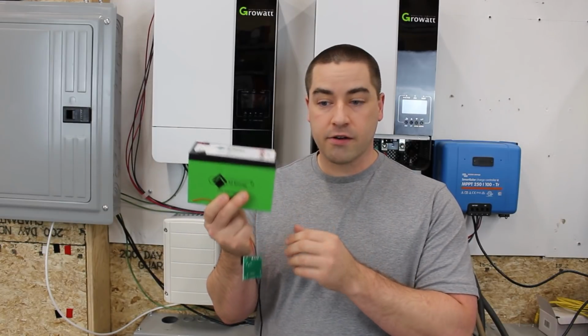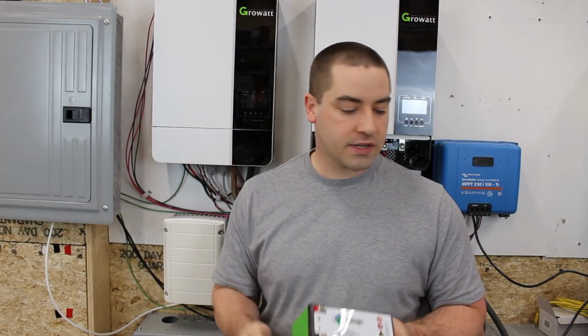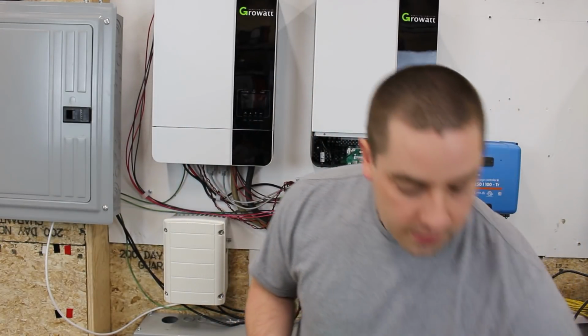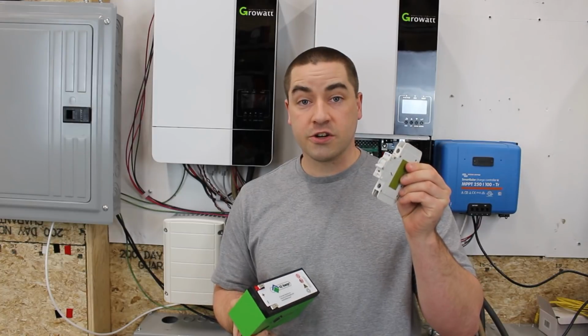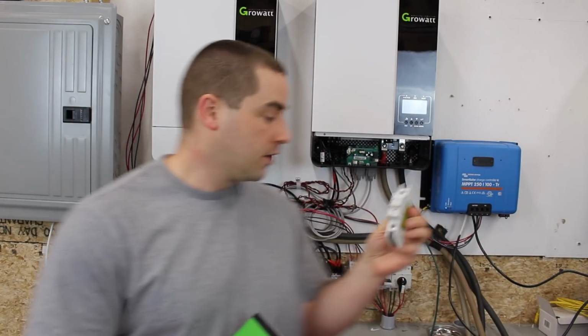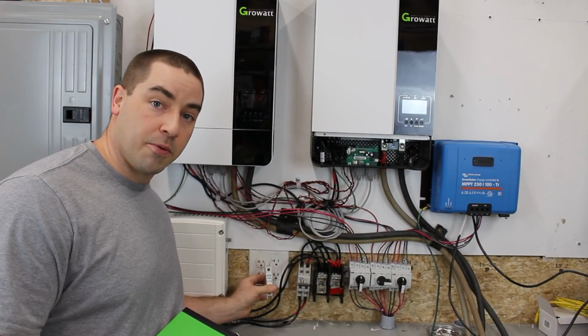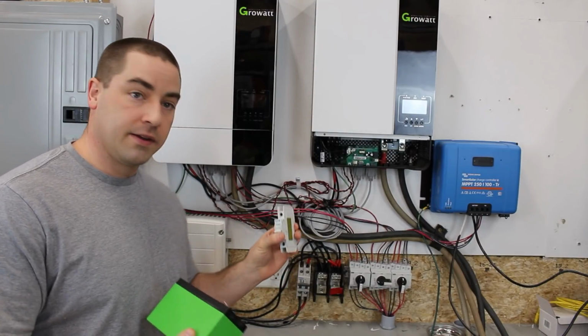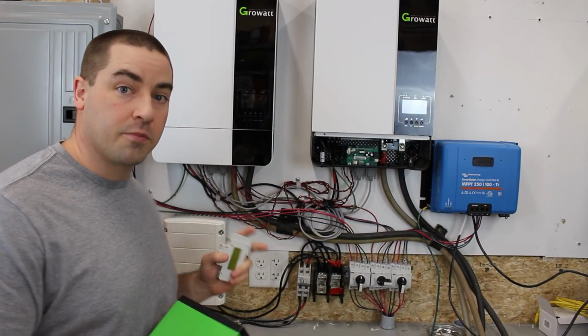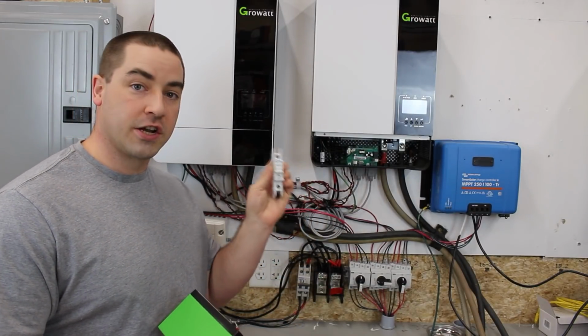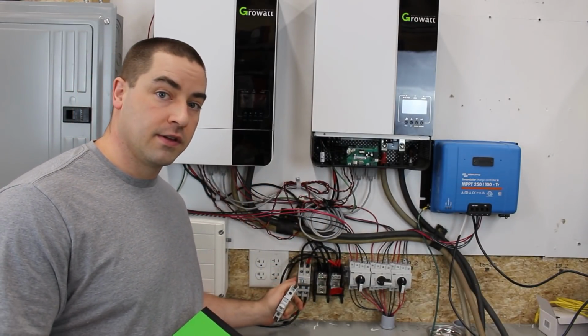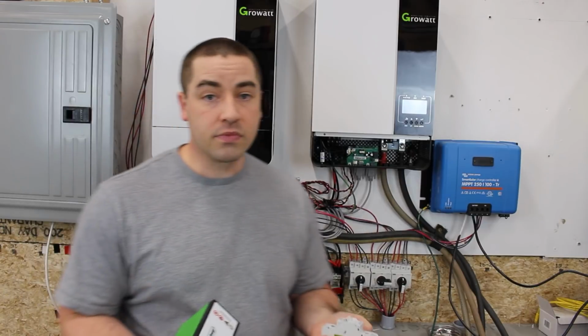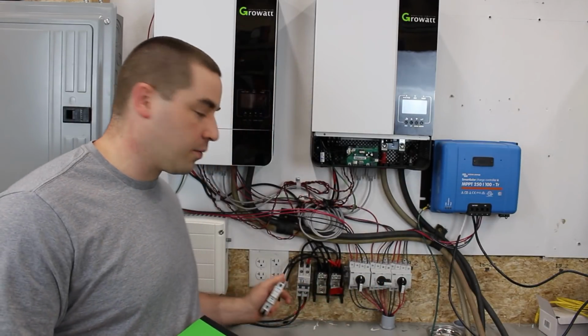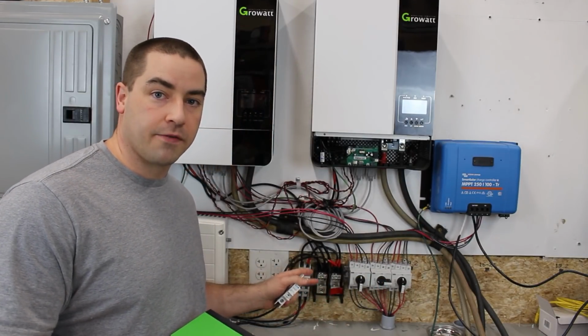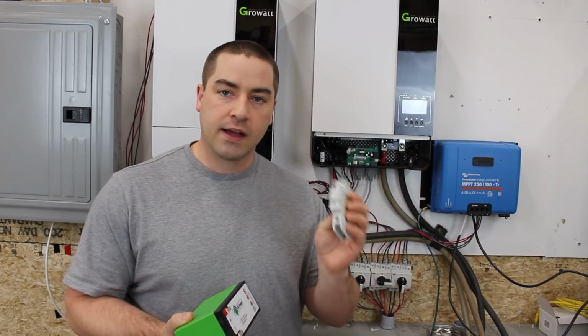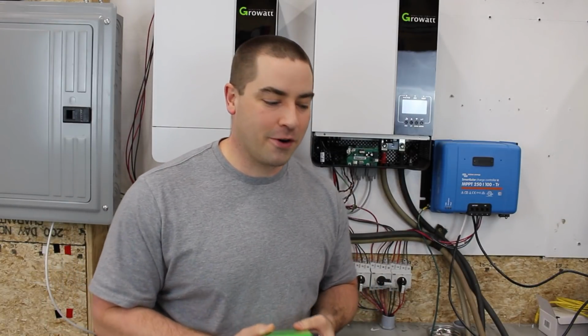So I could use a little battery like this, a little temperature sensor, and then I could use a little shunt trip circuit breaker like this one, paired up with the double pole circuit breaker. That way, if the auto transformer is getting too hot, the shunt trip shuts off the double pole breaker. So that's a way to do it. Now I would have to move some of the wiring off the terminal block to do that setup, but that was the way I was going at first.